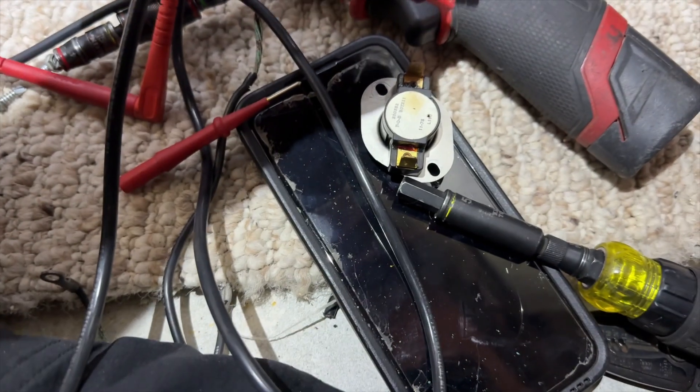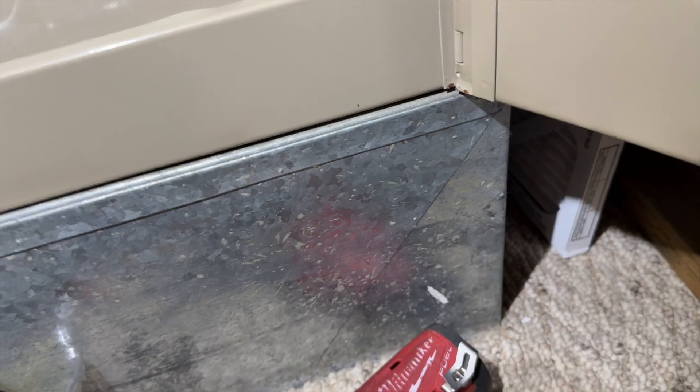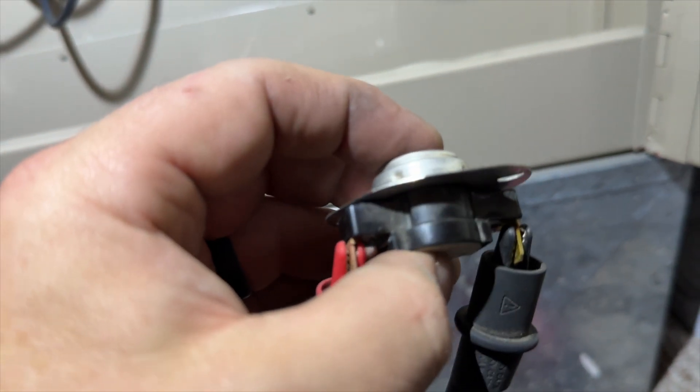So that's the one I pulled out. See, it's open. I think it's bad because it's been getting tripped multiple times because of the dirty filter. Sometimes you can smack it and that'll reset it, but we probably want to replace it. I've been trying to reset it. I think the contacts are burnt up.